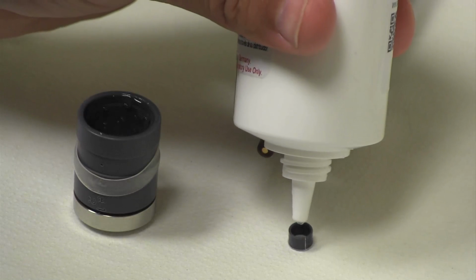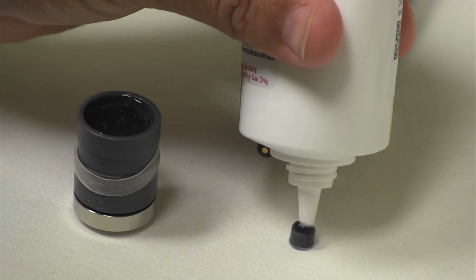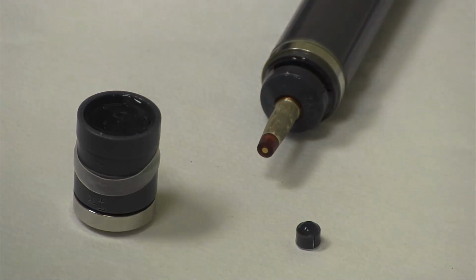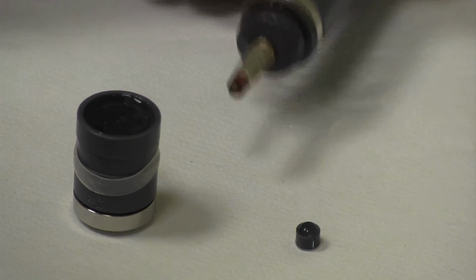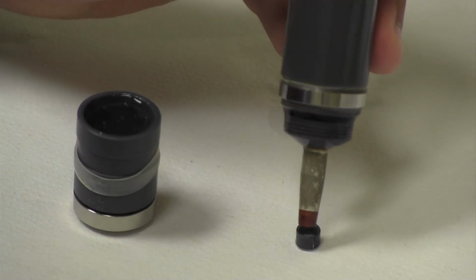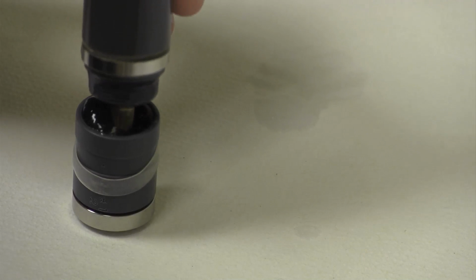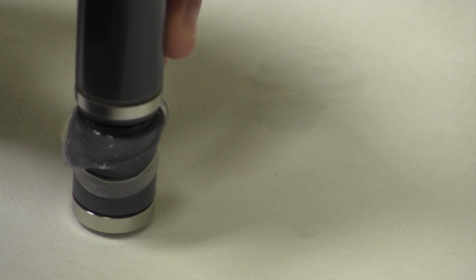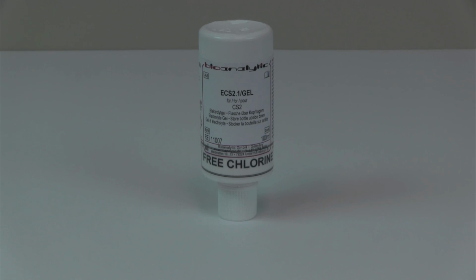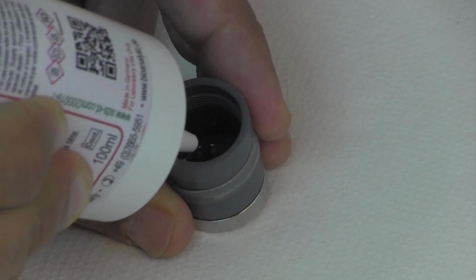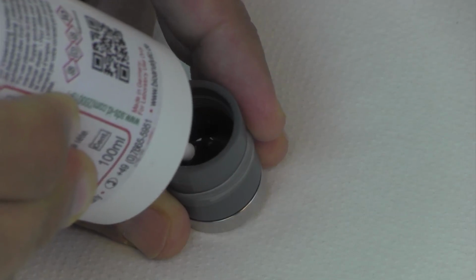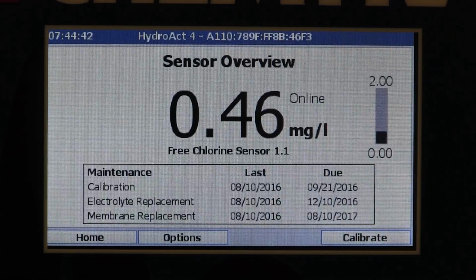For these models, before putting on the membrane cap, the G-holder is filled with electrolyte, and then the electrode tip is inserted into the G-holder. The probe, with the G-holder on the tip, is then inserted into the electrolyte-filled membrane cap. It is recommended that the electrolyte be replaced every 4 months and the membrane cap every year. The Hydroact Analyzer provides maintenance reminders for when the electrolyte and the membrane cap need replacing.